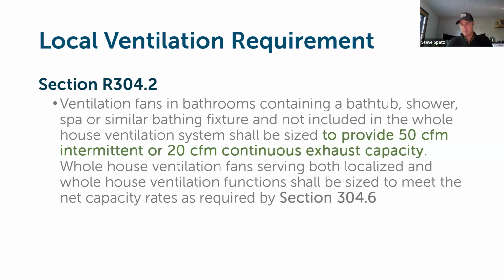When it comes on, it needs to be moving a minimum of 50 CFM. Or if it's going to be a continuously run system, a system running at a low volume throughout the day, 24/7, then it needs to meet a minimum of 20 CFM in those spaces.